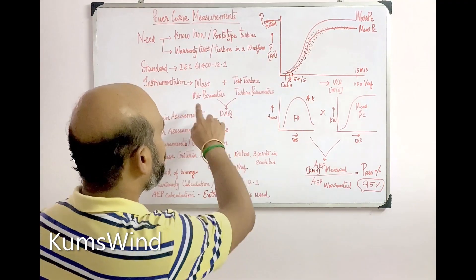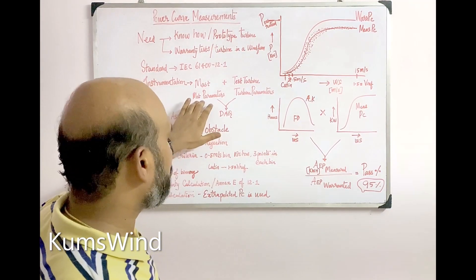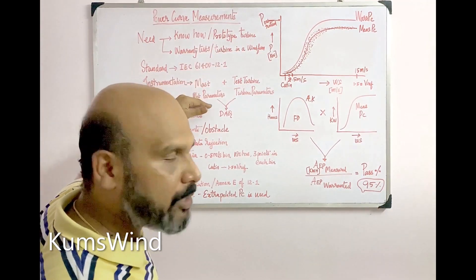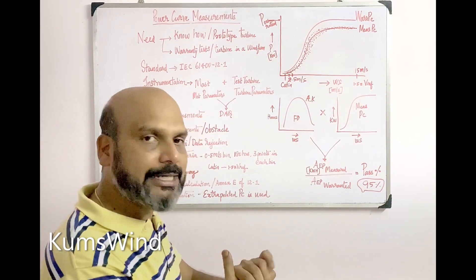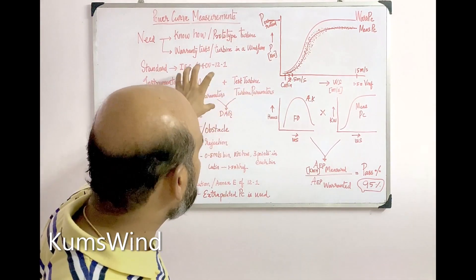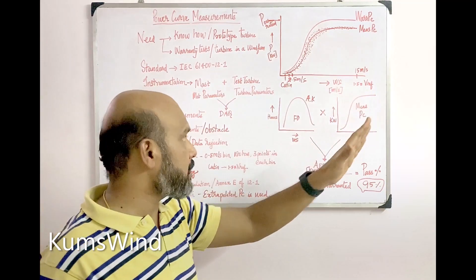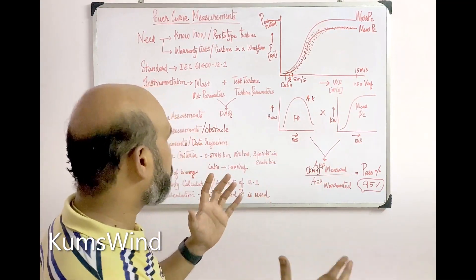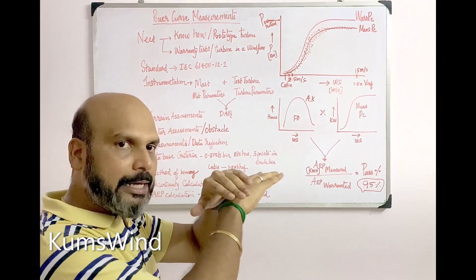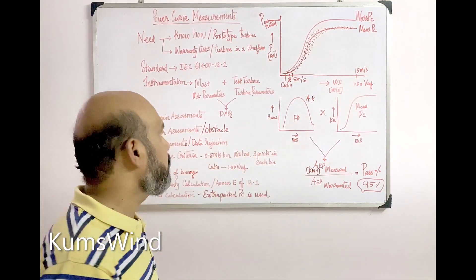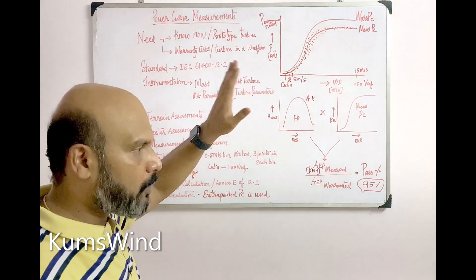From the mast you measure meteorological quantities: wind speed, wind direction, humidity, temperature, pressure, and rain, using Class 1 sensors. From the turbine side you need to measure active power, reactive power, frequency, and the operational status of the turbine. All these meteorological parameters and turbine parameters are pulled into a data acquisition system, either in the met mast or the turbine control room, collected in one data logger with one time stamp.